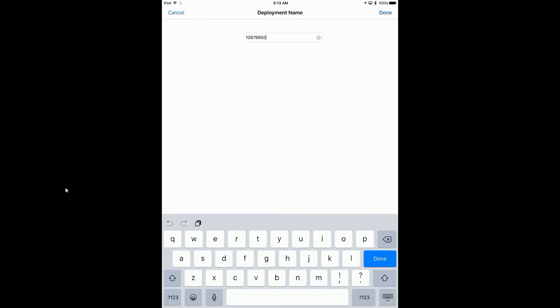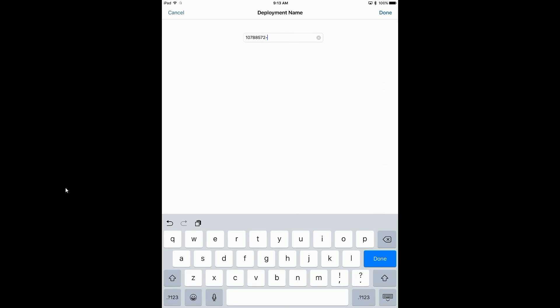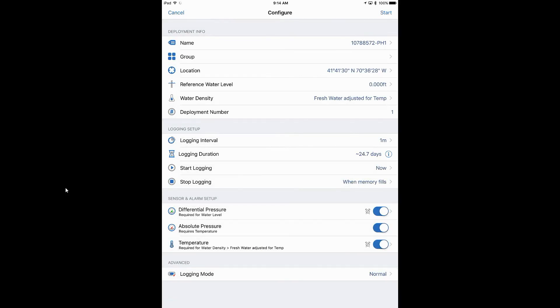We're going to give it a name. To give it a name, we just tap on the name field. The name we need to give this is 107-8-8-572. You can name this anything you'd like — this is going to be our file name when we read out the data, and this is the name that our engineer wants us to give this deployment.